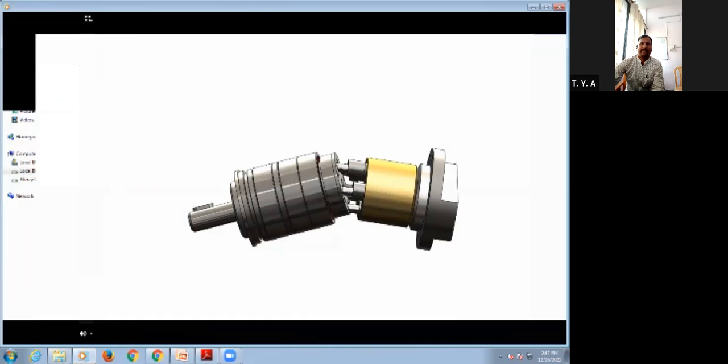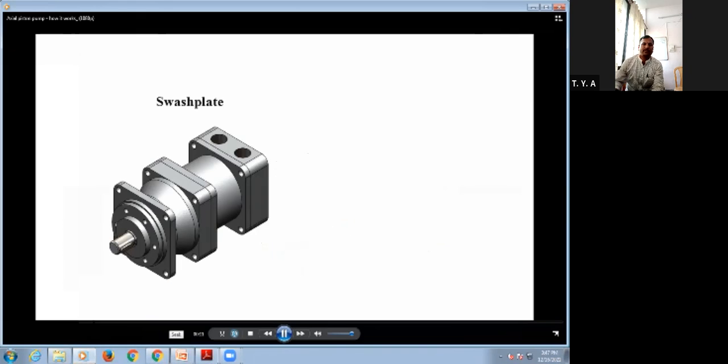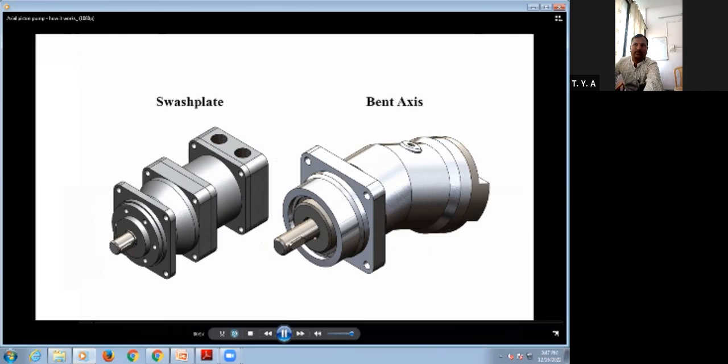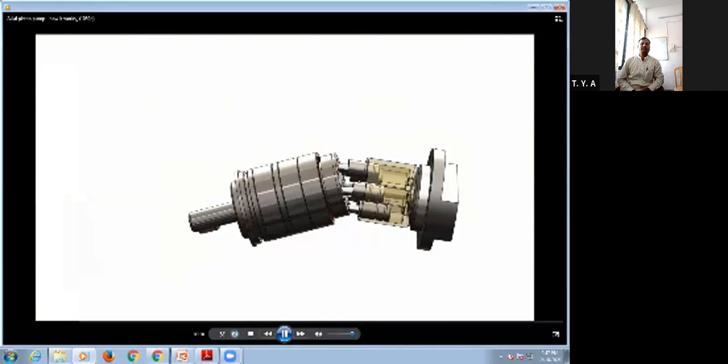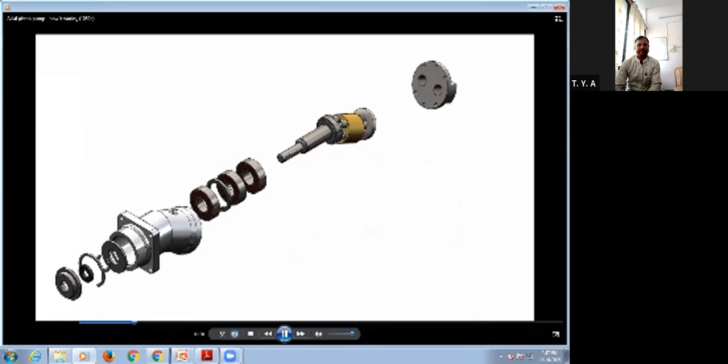An axial piston pump is a pump that has a number of pistons in a circular array within a cylinder block. There are two designs are most relevant, the swash plate configuration and the bent axis configuration. In both cases, the angle, the swash plate or the bent axis mechanism, determines the effective stroke of the piston. Bent axis pumps design. In a bent axis piston pump, the cylinder block turns with the shaft but at an offset angle. The piston rods are attached to the drive shaft flange by ball joints.